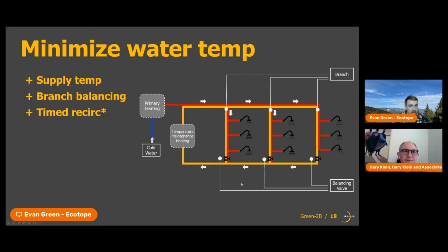Great. And the other thing we'll talk about is minimizing the water temp. So we want to decrease the supply temp as much as possible while still supplying the occupants with the proper water temperature. And the best way to do this is through branch balancing. Christoph mentioned these thermostatic balancing valves, which I think are a great way to do this, to provide just enough temperature maintenance flow in each branch to be able to satisfy these water temperatures.